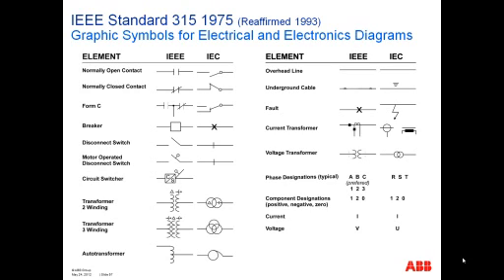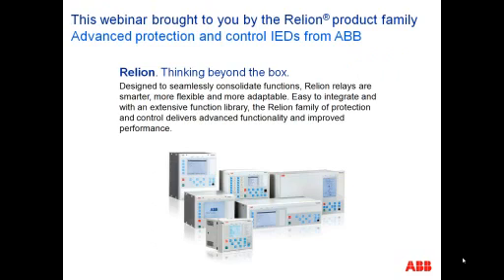You really want to learn the IEC standards as well, because a lot of what you may encounter in your careers will show things in this symbology. You have the IEEE, which is predominantly the U.S. and somewhat in Canada, but IEC is the rest of the world. But you have your normally open contact and your normally closed contact in Form Cs, and you got your transformer representation as shown down there. I've always liked the underground cable where you have a line under a ground symbol for the IEC standard. But it just is an example of how you take a set of engineers, put them in two different rooms, how they come up with something clever and good, but in two different ways.